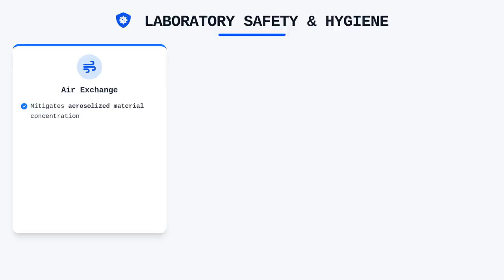Laboratory air exchange requirements are often overlooked, yet they are essential for mitigating the concentration of aerosolized material in a testing room. You should be familiar with your facility's ventilation standards, which typically require a specific number of air exchanges per hour to ensure adequate dilution of airborne contaminants.